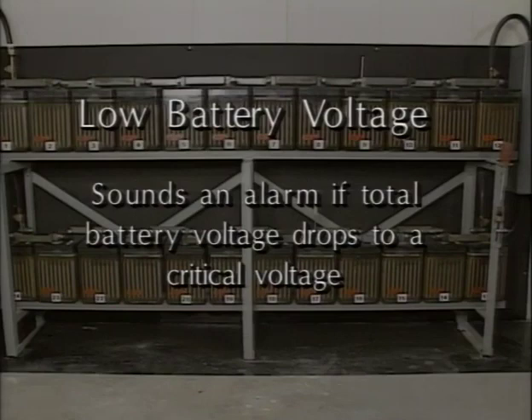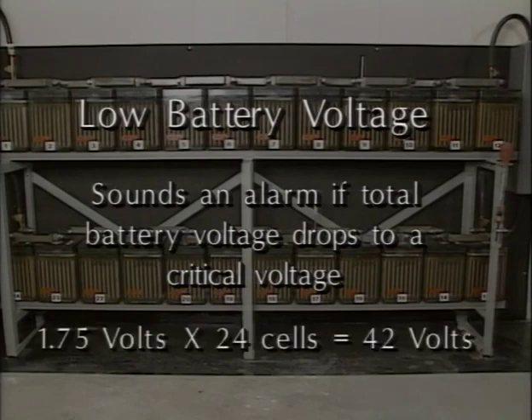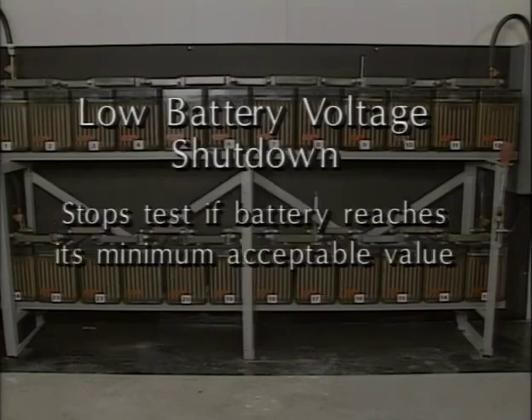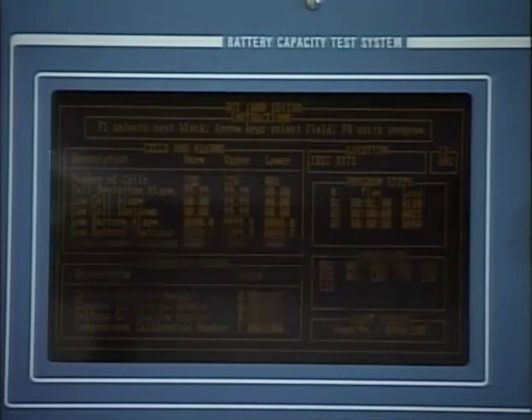Low battery voltage, to sound an alarm if the total battery voltage drops to a critical voltage, usually 1.75 volts times the number of cells, in this case 42 volts. And low battery voltage shutdown, to stop the test if the battery reaches its minimum acceptable value. In this case, the minimum value is 42 volts, the same as for the low battery voltage alarm. Some control units may include a video monitor, which visually indicates the voltage of each cell during the tests.